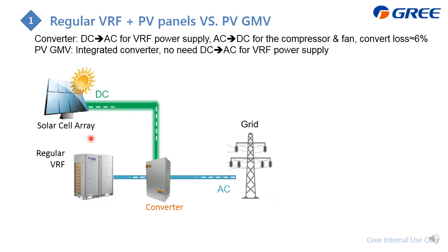You can find it on this graph. This is, for example, the regular VRF, and this is the converter. It handles the power, either from AC, from the grid power supply, or from DC, from the PV panels. So for this case, the converter needs to convert the DC to AC, then power the regular VRF. And for the compressors and fans inside, if they are DC, which is very popular, they need to convert this AC to DC again to drive the inside compressor and fans. So the total conversion loss is 6%, for 2 times.